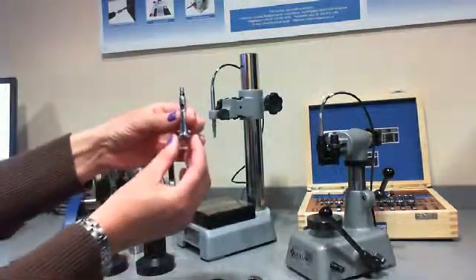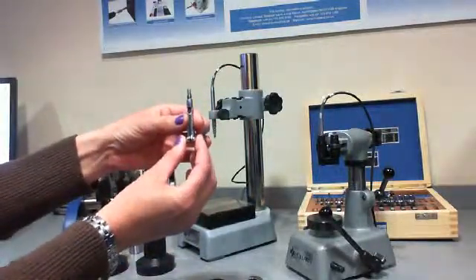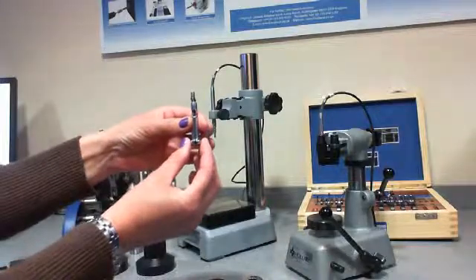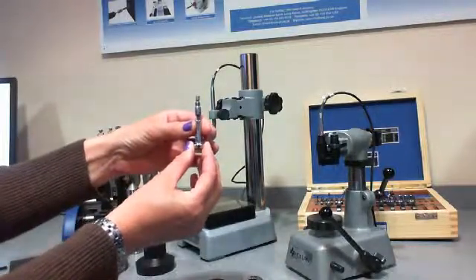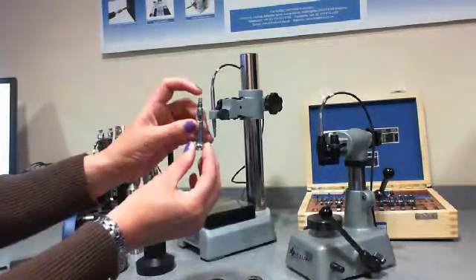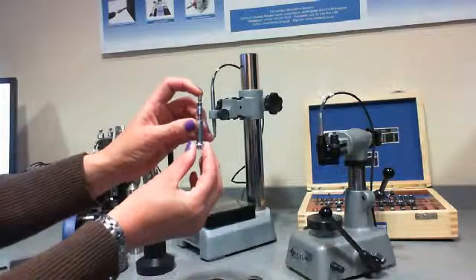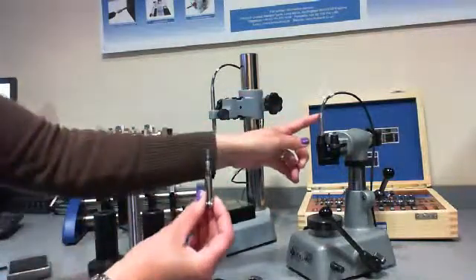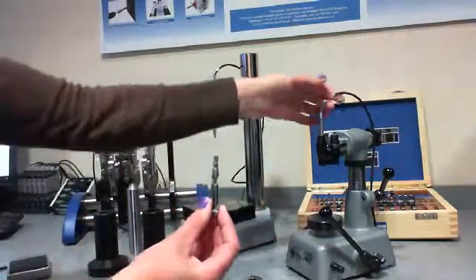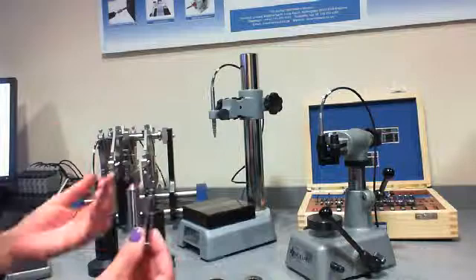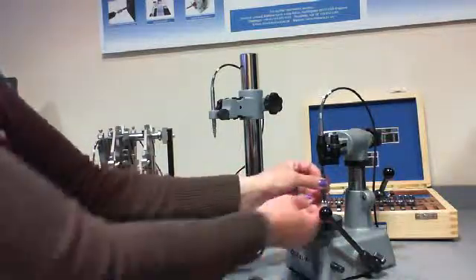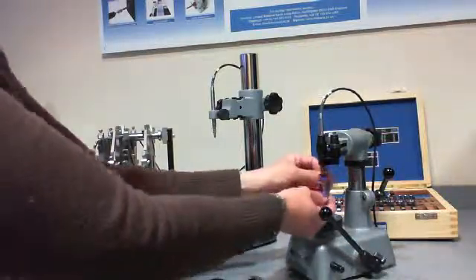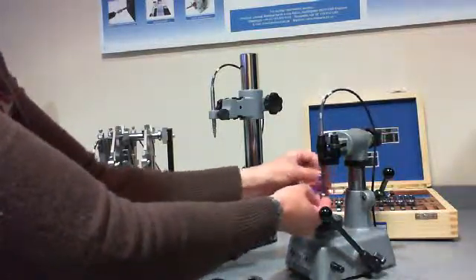What happens is as the split ball probe enters the die bore, you can see this needle point just moving up slightly. And that pushes against the probe which is locked into position here and then takes the reading. So I will just screw that in there.